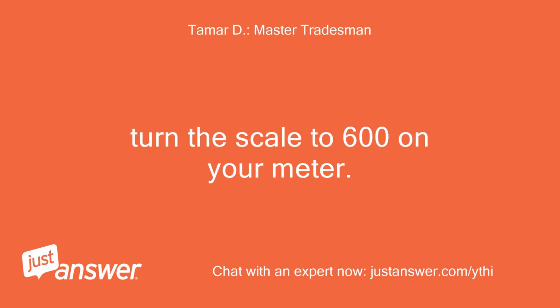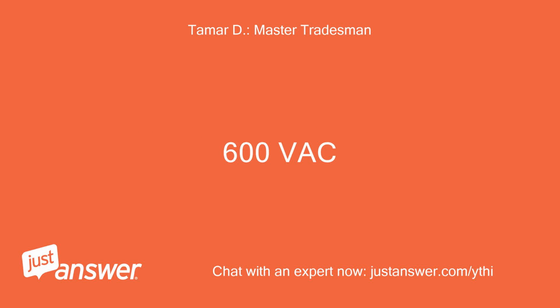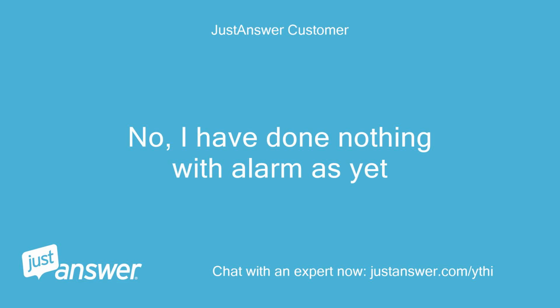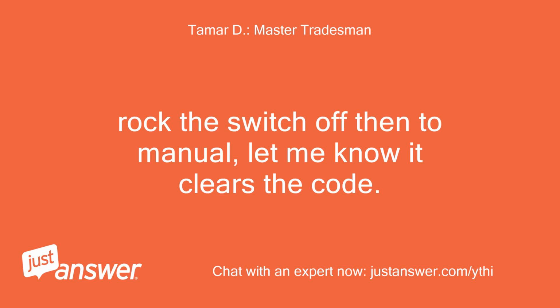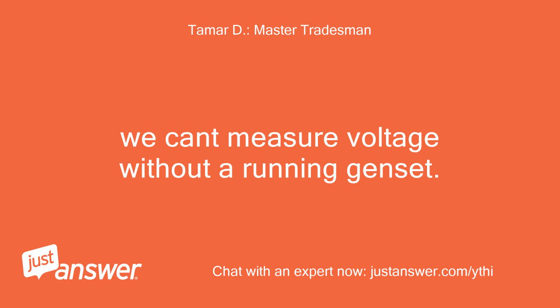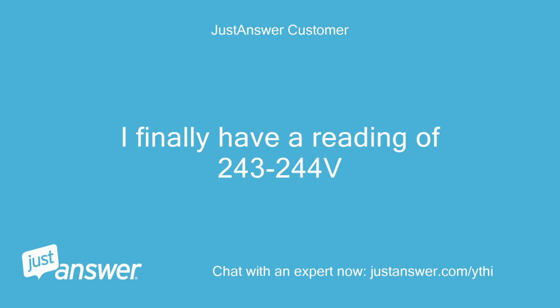Turn the scale to 600 on your meter. 600 VAC. No, I have done nothing with the alarm as yet. Rock the switch off, then to manual. Let me know if it clears the code. We can't measure voltage without a running genset. I finally have a reading of 243 to 244 volts.